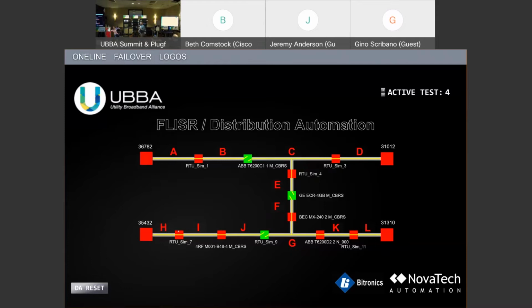That reverse function happens once the repair is made and we want to restore service to all those customers. Sometimes that's a single button you push that says reverse. Sometimes it's manual, with SCADA operators going in, and here's an interesting thing: for short periods of time we will close after we've repaired and the grid's back together, feeding a bus from two ends.